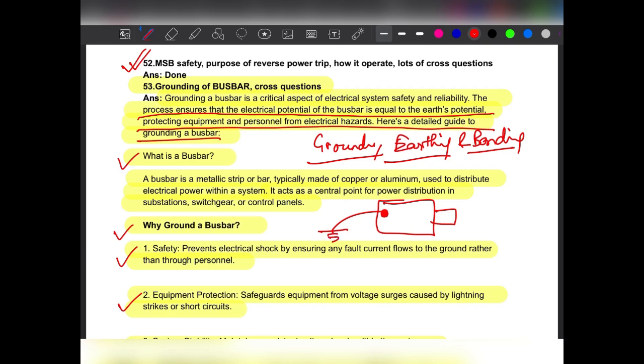So why are we doing this? To protect, because if there is any fault in a motor and somebody directly touches it, they may get a shock, so we have to properly ground this fault current. So we just connect the motor enclosure to the ground. So we are doing this earthing. And bonding, basically we do to maintain the equipotential.